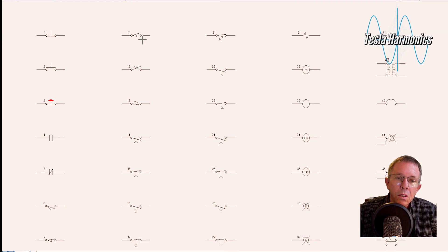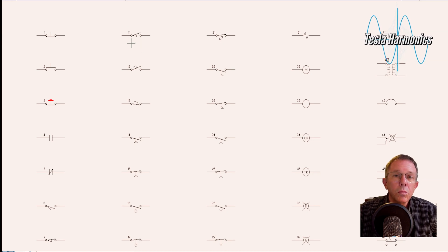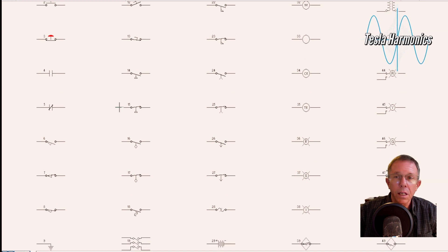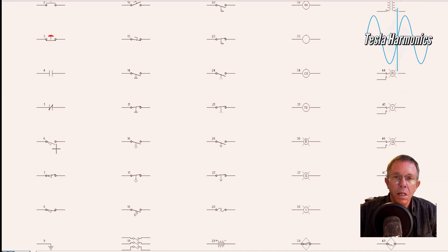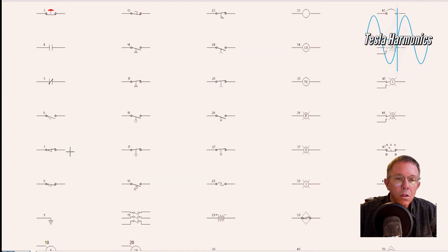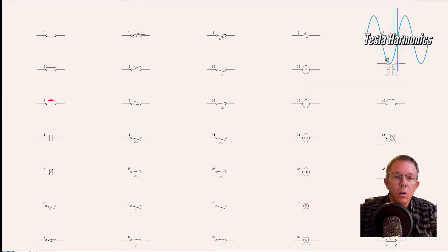Number 11 is above the circles, so it started off as a normally closed, but it's being held off the circles. That makes this one a normally closed, held open limit switch. Those rules only apply to limit switches — if it is hanging below the circles, that is normally open; if it is sitting on top of the circle or the contact, then it's normally closed. And it can be held closed or held open.